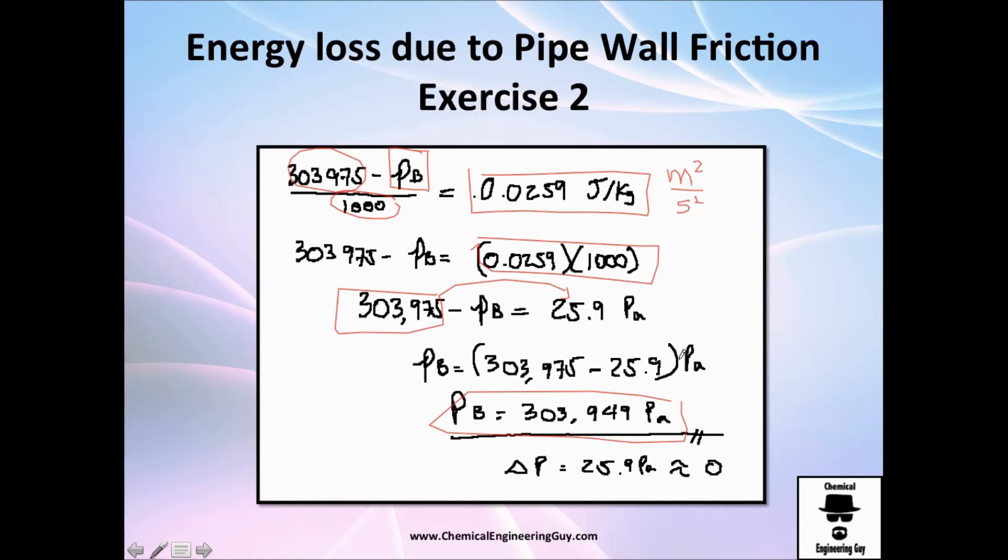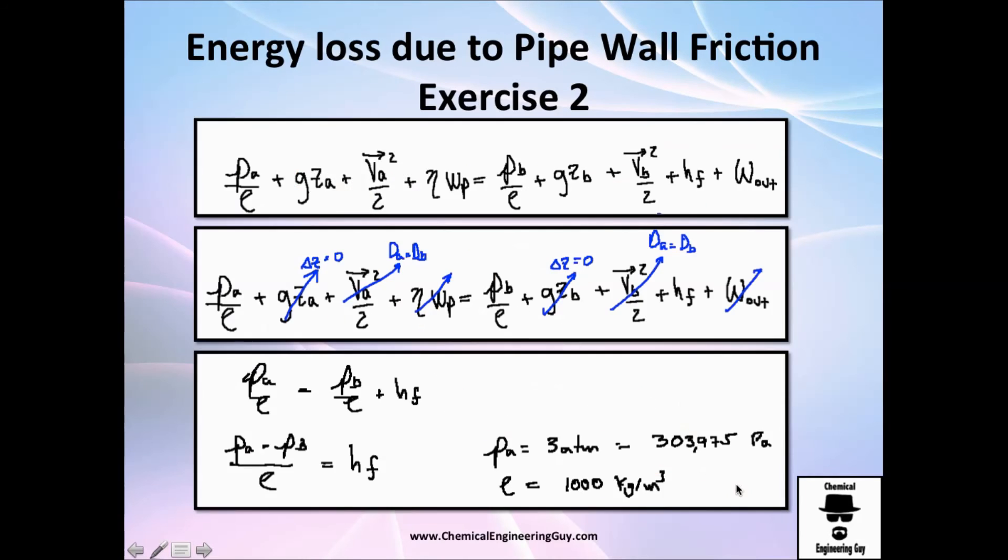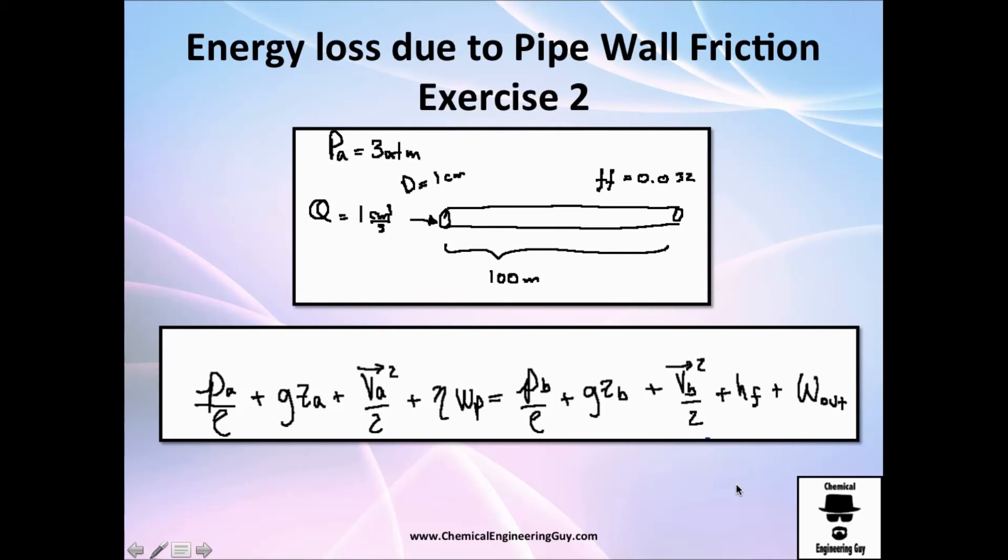So guys, in this case, you can see, it's not that big the energy loss. We got a 25.9 Pascal, which is almost nothing, guys. So it's good. This is due to that we have a very small flow here. We have a small flow. And the diameter is relatively small.